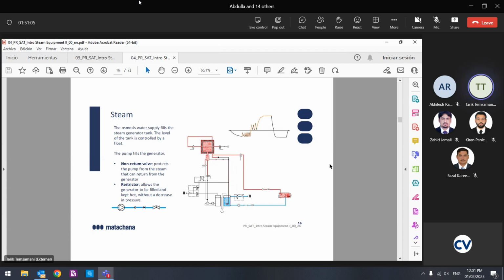So the osmosis water supply fills the steam generator tank. The level of the tank is controlled by a float, and the pump fills the generator. Now it seems easy, but it's not like that. First we need RO water, and with it we fill this tank. This tank has a level float. It doesn't have a water temperature sensor, unlike the vacuum tank, which has a temperature sensor. Then we have the filling pump, a one-way valve, a restrictor, and then a manual valve in case we have to change something in the steam generator.